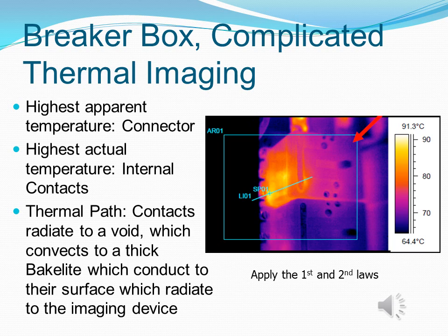There's a little bit of air in there, right? The air convects, becomes hot, eventually becomes stable, and that further oxidizes those contacts, making even more of a problem. But some of that convects into the bakelite that is the box itself. It's a black or gray or brown box, and then poorly through that bakelite. Remember, the conductivity was very low. It was 0.21 through that bakelite and out to the imaging device.